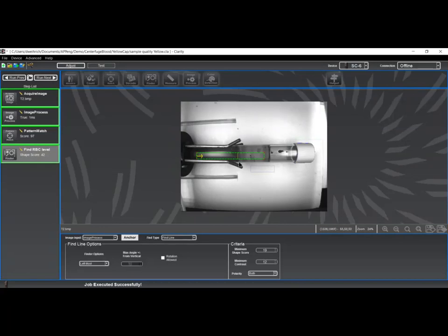Again, we're looking for a line. We're finding a line that goes from darker to lighter. It has a reasonable distinctness. These are all parameters that experimentally are worked through here using contrast adjustment and shape and length. And of course I'm looking for the first transition, which is the blood to serum transition, so it is the leftmost transition.